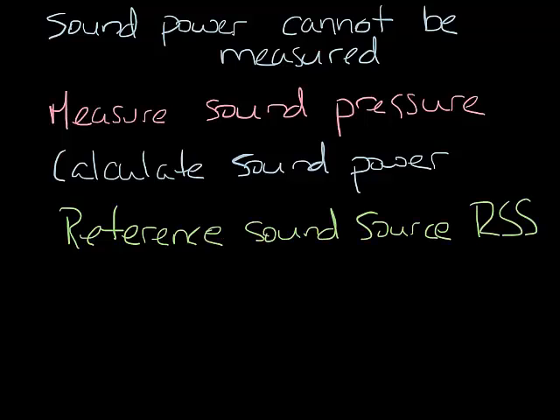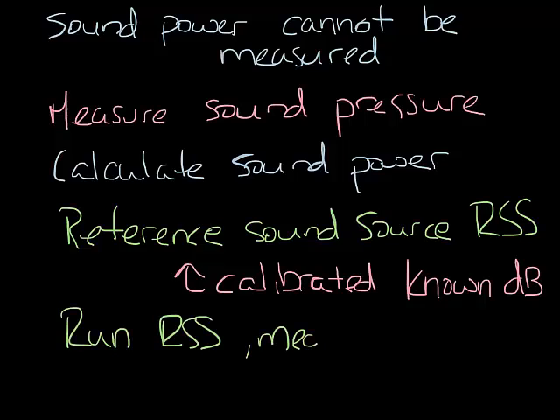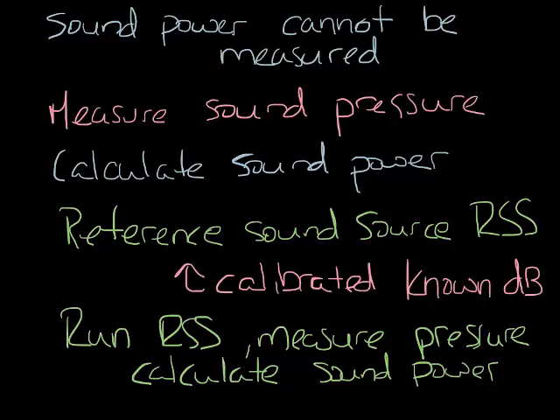The RSS is calibrated to a known sound power, say 80 dB in every band. Then when you take sound pressure readings in the sound room you can calculate the difference between the known RSS data and the measured sound pressure and then you know how to correct for test data you take later in that room.